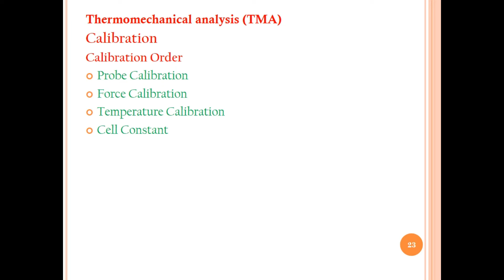First of all, the probe calibration. Calibrate the LVDT. LVDT is again the sensor for the expansion and the contraction, meaning the length measurement sensor, and adjust the force calibration factor to compensate for differences in the mass of various probe types. Perform every time a probe is changed or installed. The calibration of the probe must be done when we install a new probe in our TMA. So every time we have to calibrate the probe to start a new experiment in TMA when we install a new probe. It is mandatory.